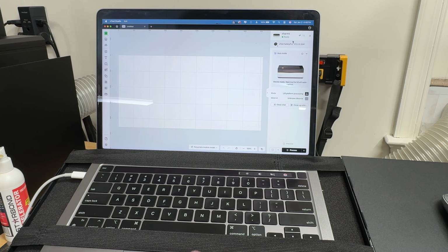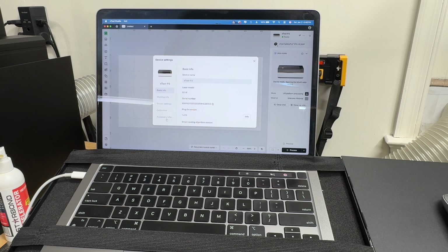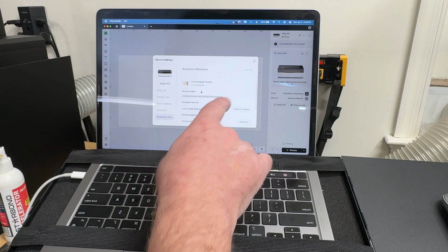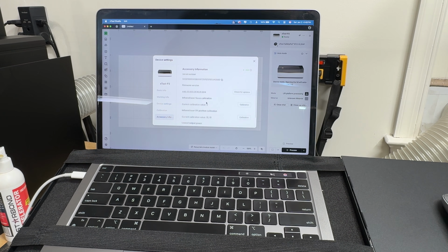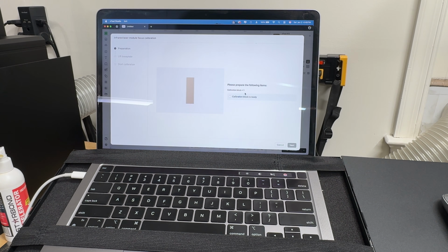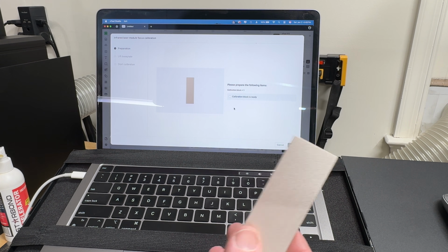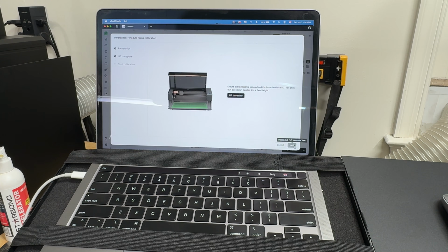So you're gonna wanna go up to the top box up top here, go to device settings, and then we're gonna come down to the bottom selection where it says accessories. And scroll down and you should see your laser infrared module. Then we're gonna go over here to the very first calibration test and we're gonna click that. Now it's gonna say, please prepare the following items. Calibration block, and when the block is ready. So we got our calibration block and we're gonna click next.